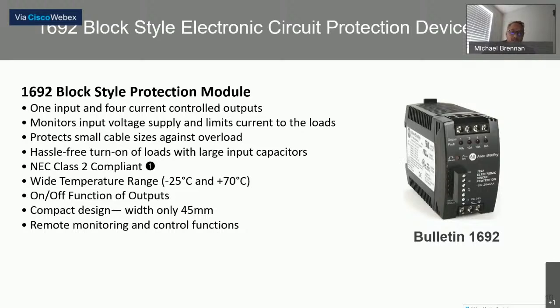So one of the things that this block style does offer is there's already a hardwired input that you can wire directly back to the PLC if there's a fault on each one of these circuits. Additionally, you'll notice that there's an LED for each output. So if there was a fault, you'll know by LED which branch of that circuit has faulted. You'll know where there's a short. You'll know if there's an individual issue. Additionally, there's a reset button that you can press on the unit if you've had a fault and you want to test to make sure the fault is cleared.